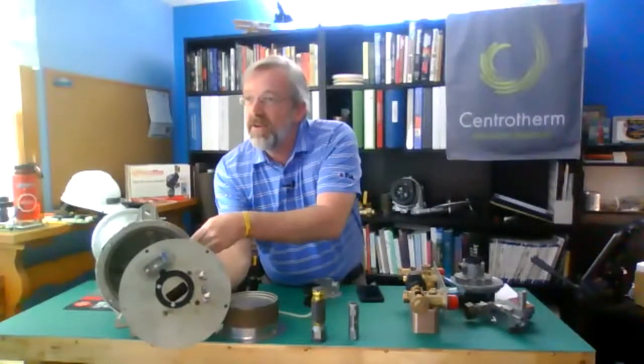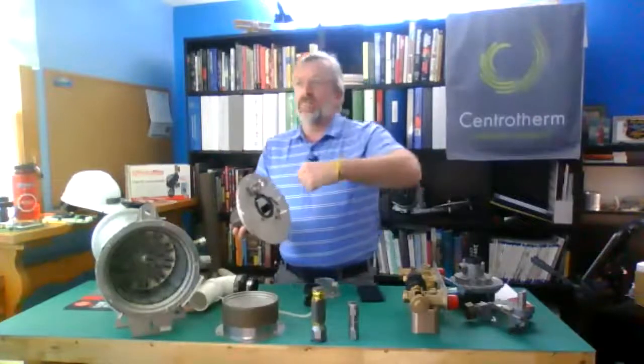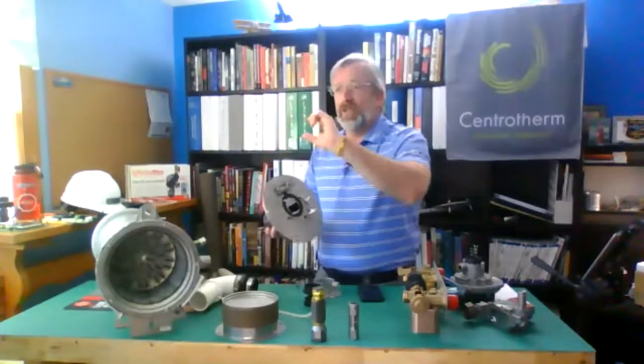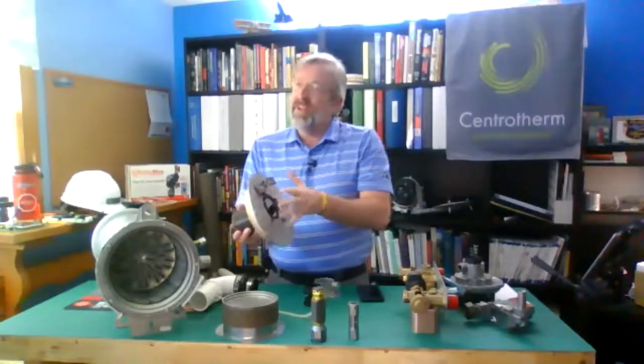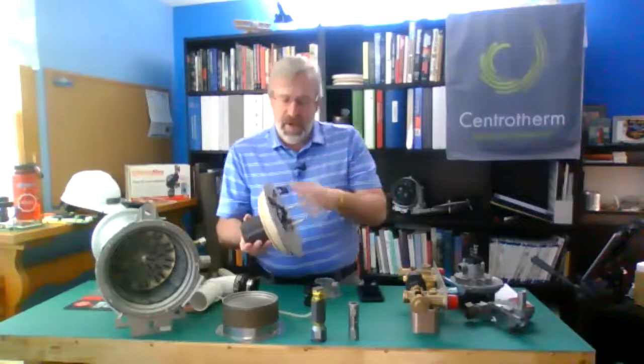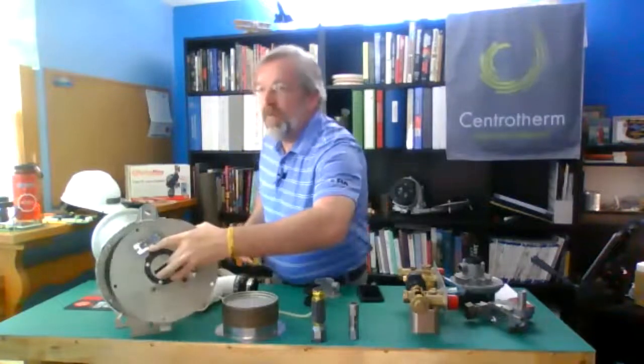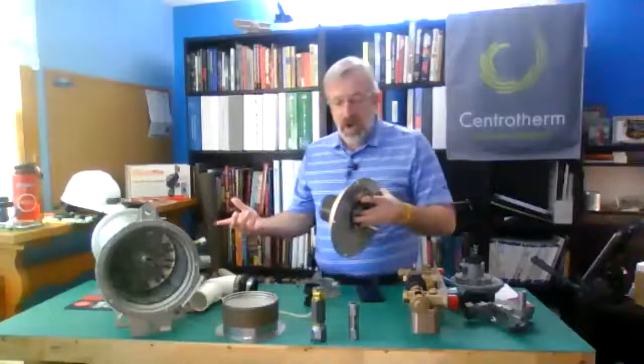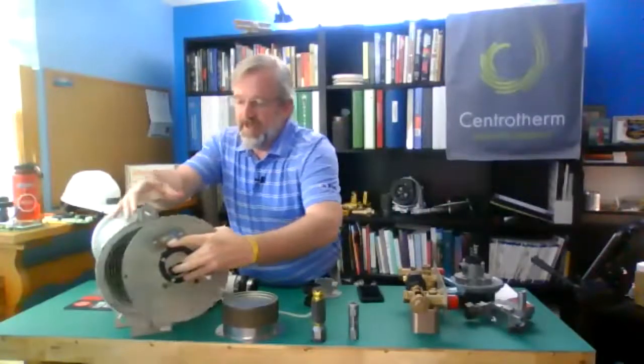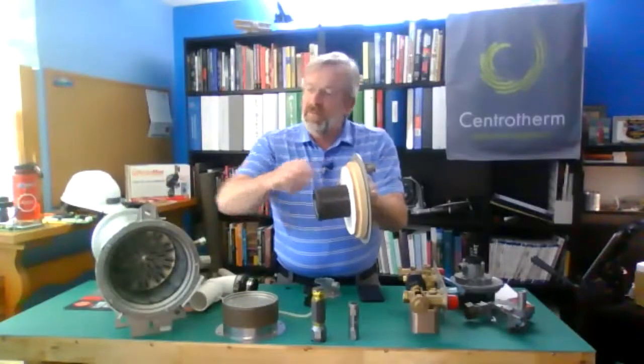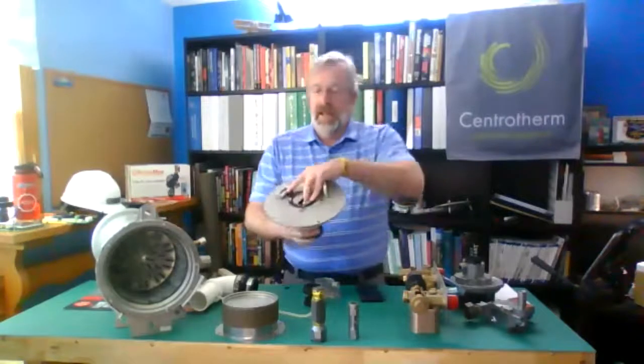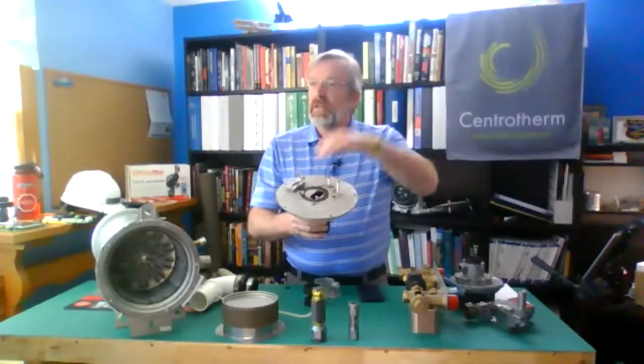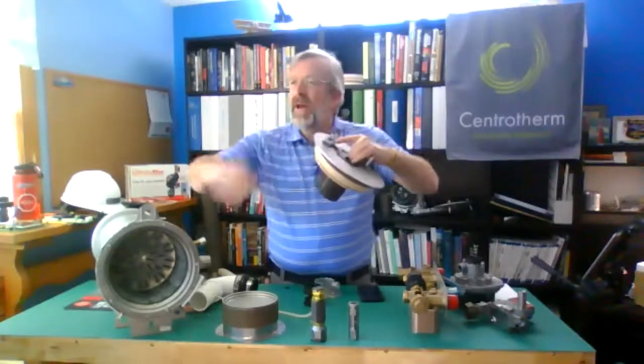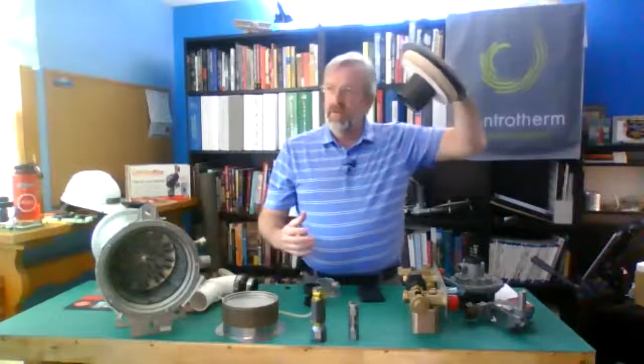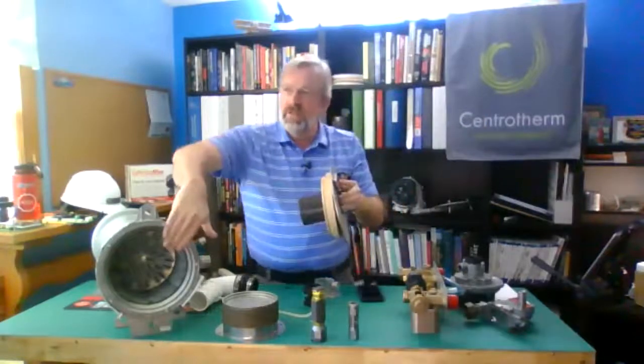take your 10mm nuts off right here. We want to do that like we're changing a spare tire, okay? First, we want to loosen them all just a bit, just in case we have any torsion on this top plate or through that gas pipe. Just give them all just a little bit. And then we take them all off, again, still staying in that pattern. And I'm going to pull this guy out. Now, note of caution. When you pull it out sometimes, especially if it's been there a little bit, this refractory sometimes likes to stick. If it's sticking, take your igniter and flame sensor out. Kind of reach in there a little bit and just hold it down, let it stay, and pull the burner assembly out. You don't want to break it, so just let it hold in place.